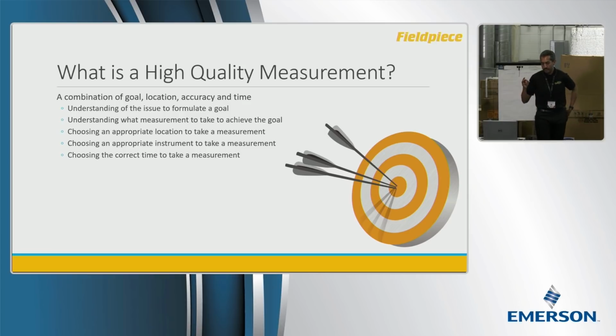Number three, we need to know the best location to take a measurement. If I'm taking a measurement because I suspect a refrigerant charge issue, and I want to take a subcooling reading because I have a TXV metering device, I'm not going to take pressures and temperatures on the suction line, right? So location is key. Also... well, that's enough on that for now.